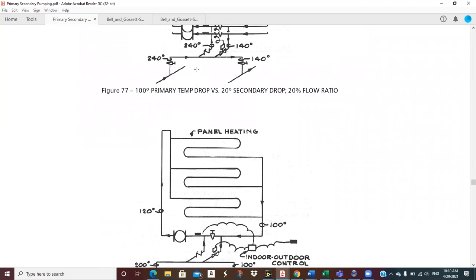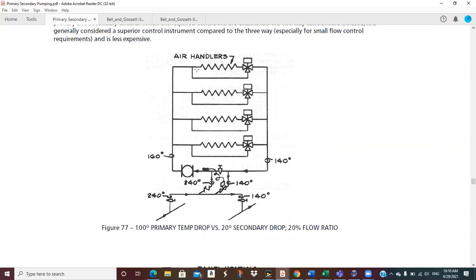And I guess we didn't really look at what's going on. But so this could be multi-story, or this could be all on the same floor and we're just showing it vertical, but we've got 1, 2, 3, 4 air handlers and we're supplying this heating water, 160-degree water to the air handlers for space heating. And they've got, what's that? That's 2 innies and 1 outie. Is that a mixing valve or a diverting valve? I think that's a mixing valve, isn't it? On the downstream side, I don't know, I forget. Anyway, it's 2 innies and 1 outie, whatever kind of valve that is, because we can come in on this side, we come in on this side, and come out on this side.